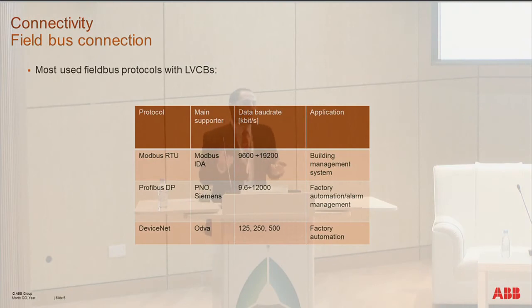So again, the first point to focus on in the smart grid is that our circuit breakers can provide communication through around 7 protocols in the communication networks. Frankly speaking, it's a huge number of protocols that we can support. The three basic protocols that we can support are Modbus RTU, Profibus DP, and DeviceNet.